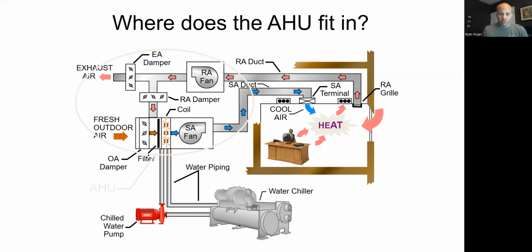So there are just two places we can go, obviously. We can go look for a chiller if you know what you're looking for, or if we're already looking at a particular zone of a building, a particular tenant space, we'll look at the air handler, because you may be looking at just one floor of a 20-story building, and you don't know if each floor has a condensing unit outside or if there's one big chiller plant for everybody. And you may not have access to the roof and things like that, but you will have access to the tenant you're working with, hopefully. So you're going to look at the air handling system.